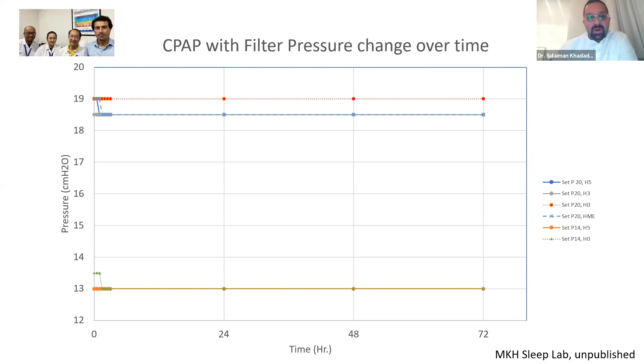And this is using a closed circuit actually, so the humidity is not dissipated. It seems that the pressure we record through the filters is consistent for at least 72 hours of continuous usage. And whether you use a pressure of 14 or 20, there's a difference of maximum 1 to 1.5 centimeters of water. And it also depends on how you set up the filter.